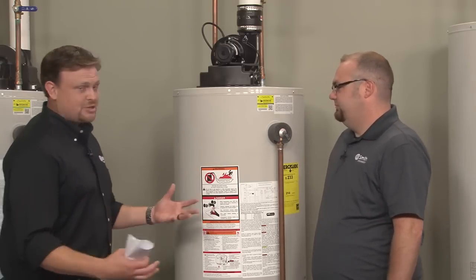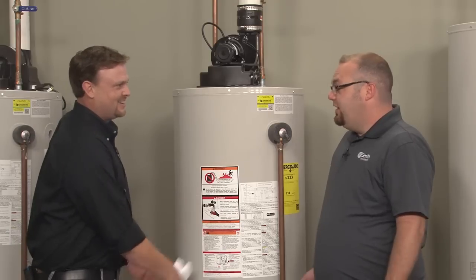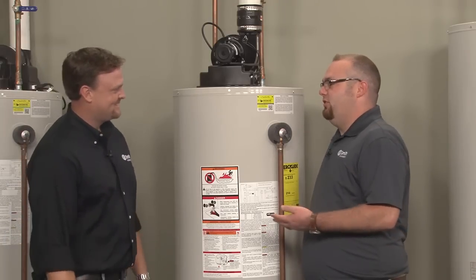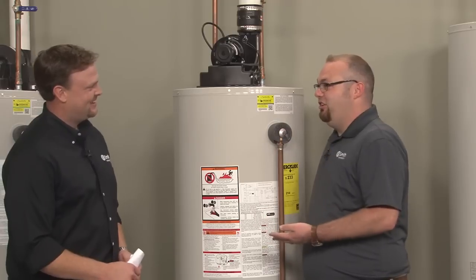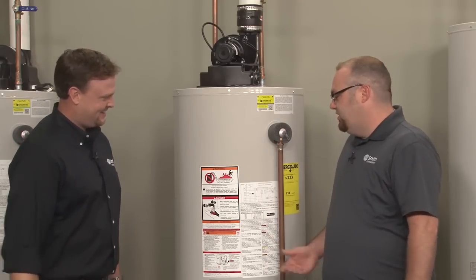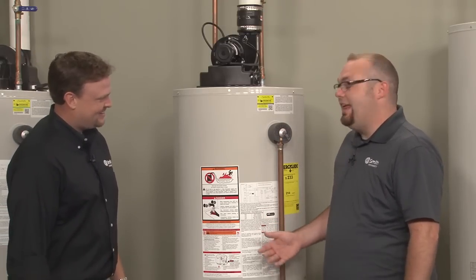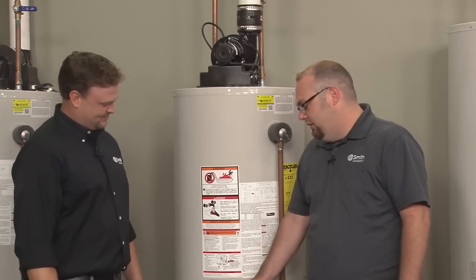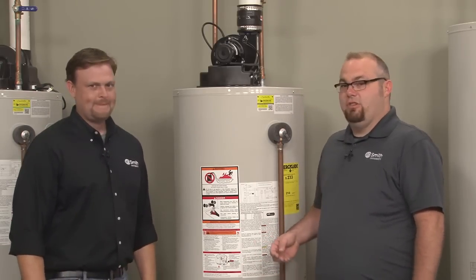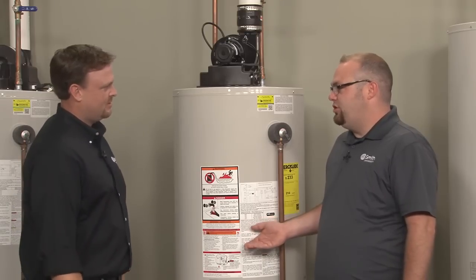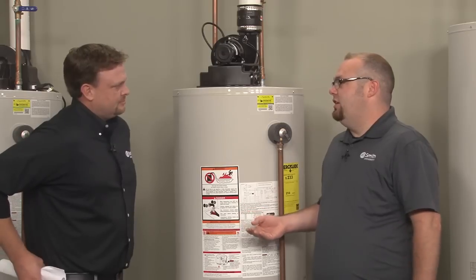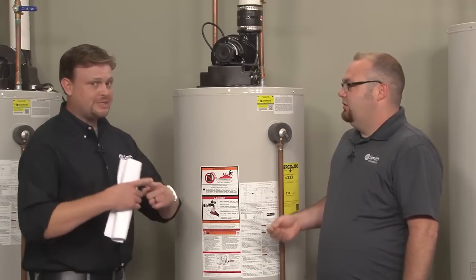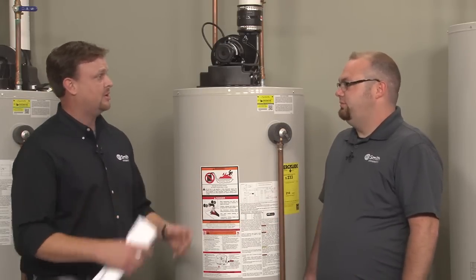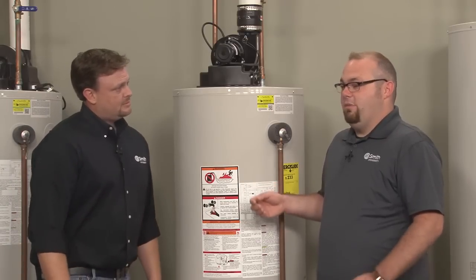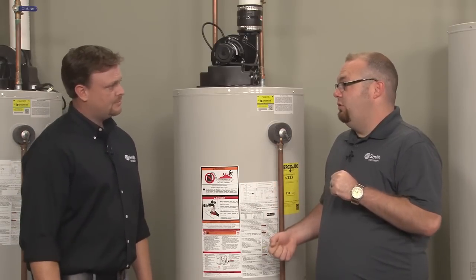I'm assuming the first thing that has to happen is you have to have a call for heat. Yes, meaning it needs to kick on and heat water. The next thing that happens is the control valve, which is like a computer, checks for the proper positioning of certain switches. One is your air pressure switch, or blower prover switch. The other is the vent limit switch. Those two are tied together, so it's just looking at that circuit. Correct. It's looking at the circuit to make sure that it proves open, to make sure no one has bypassed it.